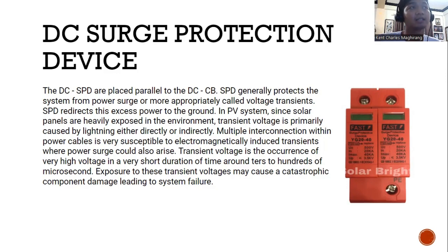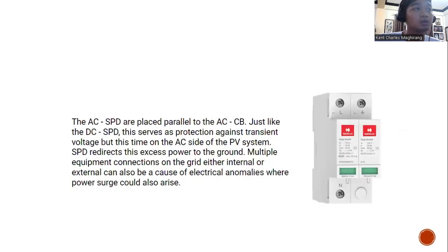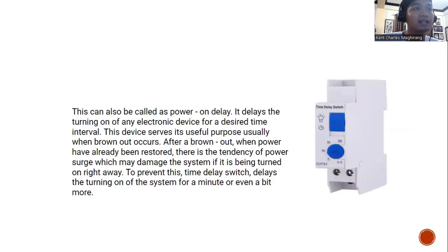voltage transient. So the AC SPD is placed parallel to the AC CB. Just like the DC SPD, this serves as protection against transient voltage. But this time, on the AC side of the PV system, the SPD redirects the excess power to the ground. Multiple equipment connections on the grid, either internal or external, can also be a cause of electrical anomalies where a power surge could also arise.